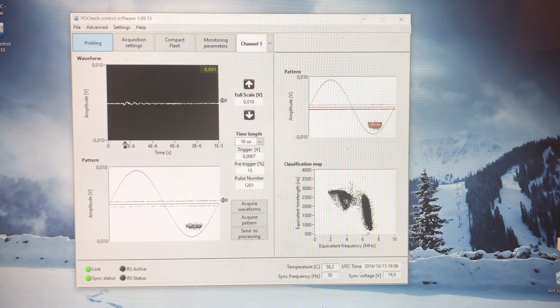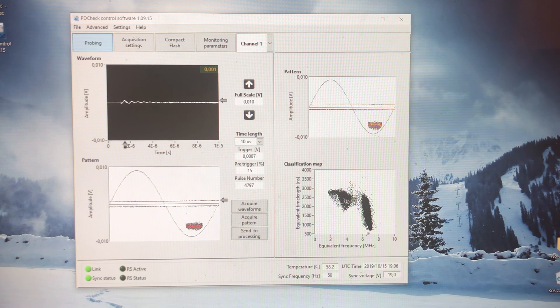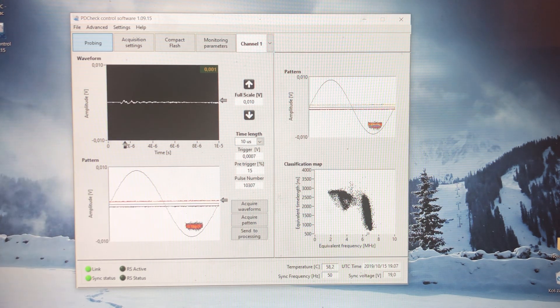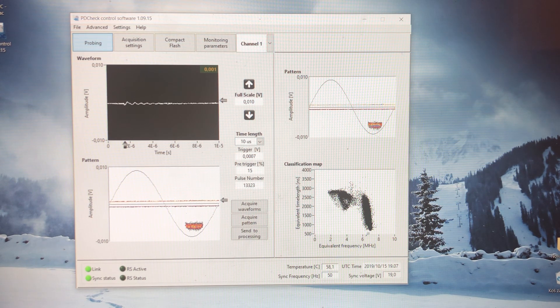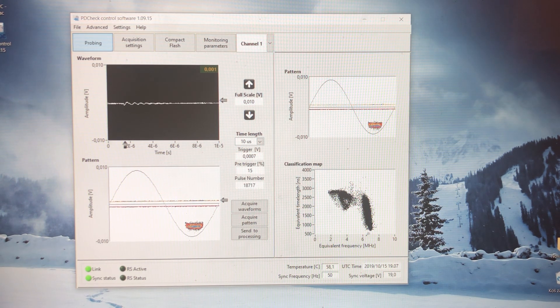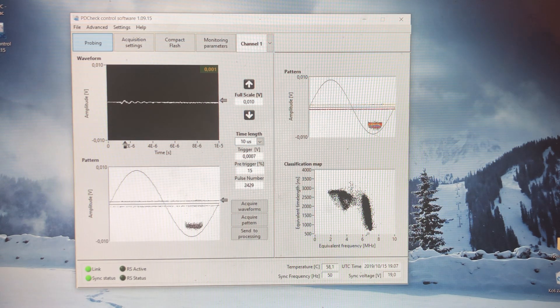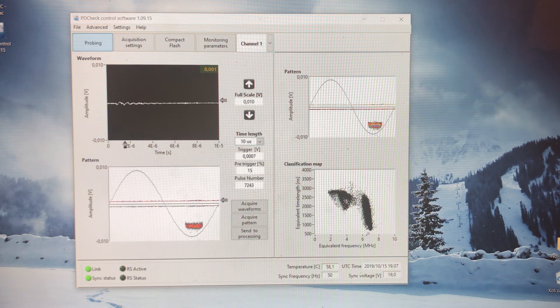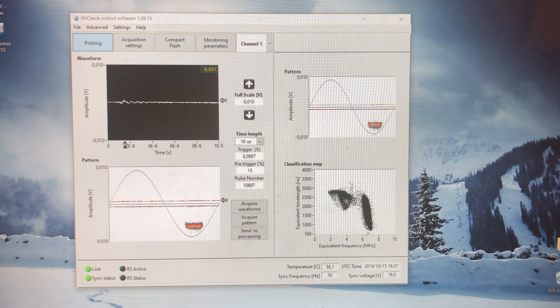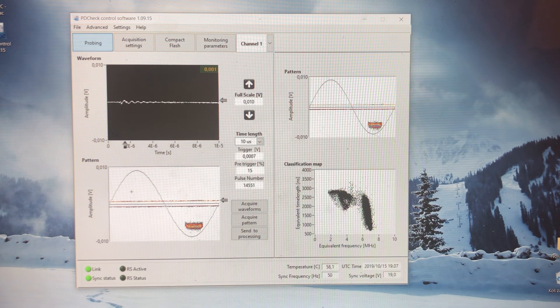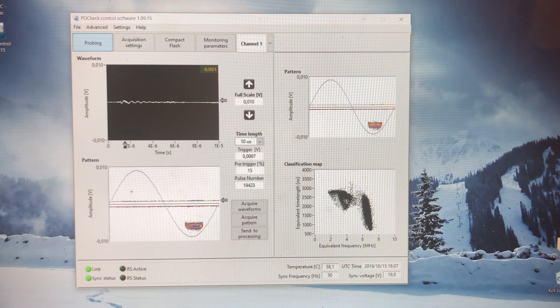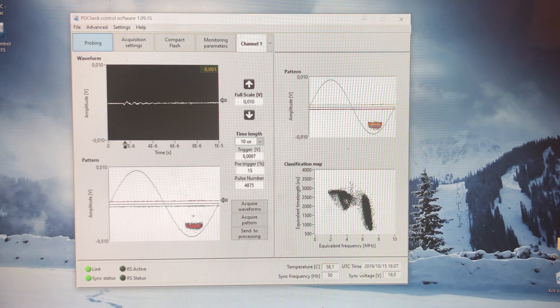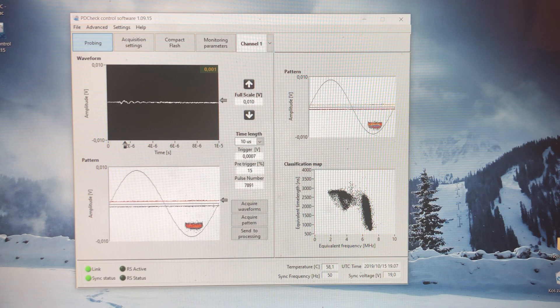We know, by the way, that this signal here is corona because, first of all, it is markedly asymmetric, which means we don't have anything on the positive side, which would be in the positive half cycle. Second of all, we see that it's very much detached from the trigger level. This is our trigger level—this is another characteristic of corona.